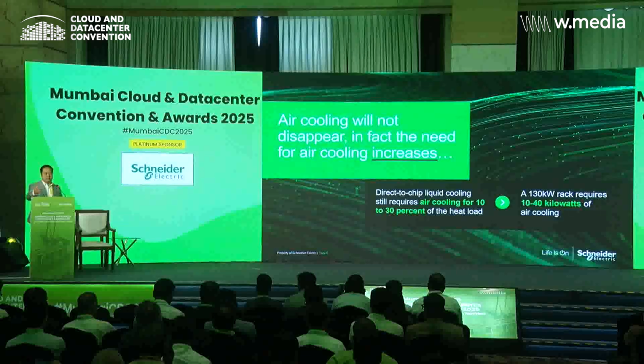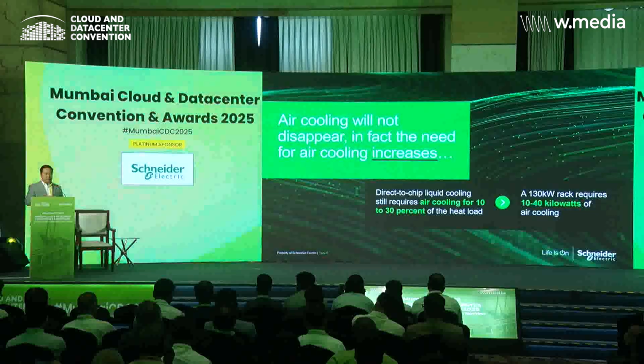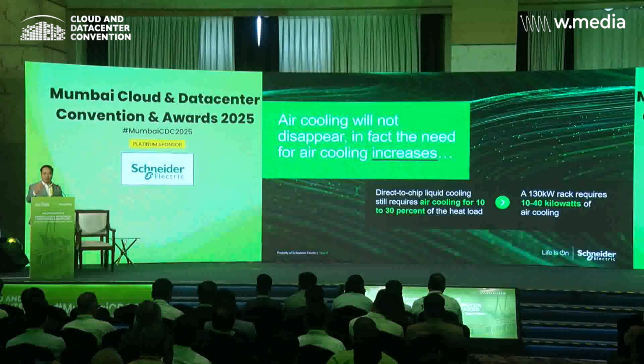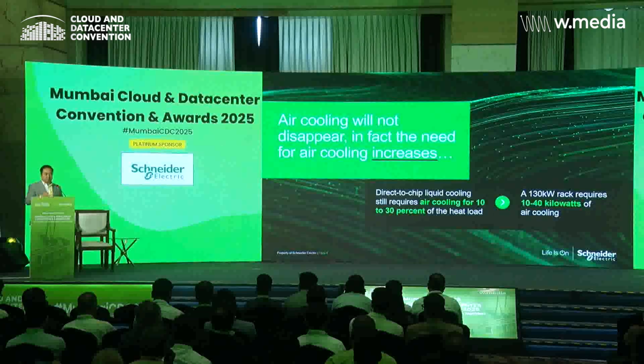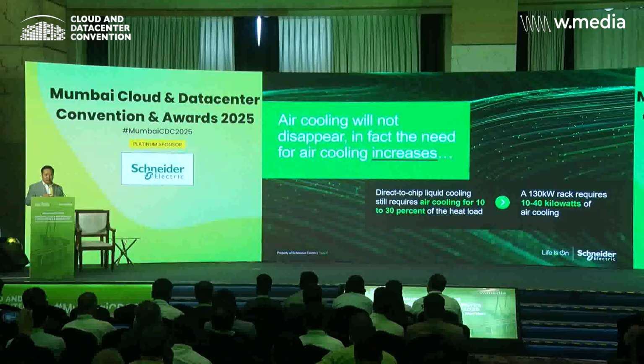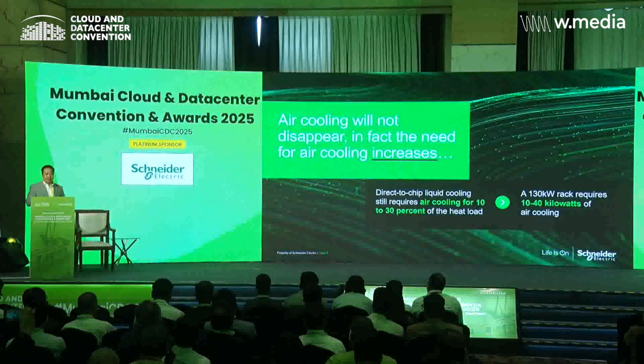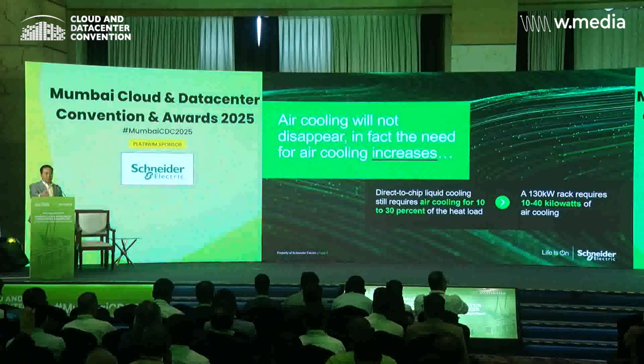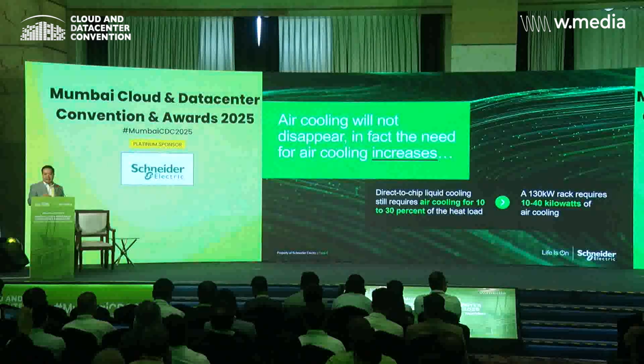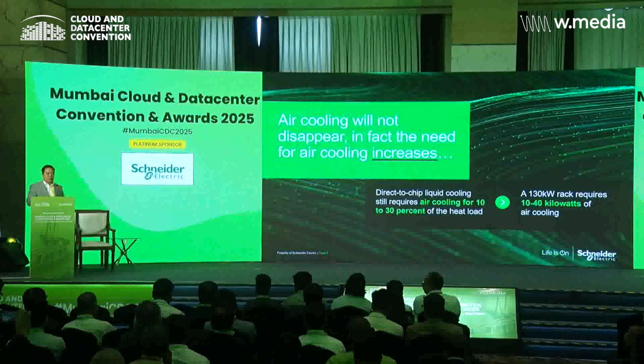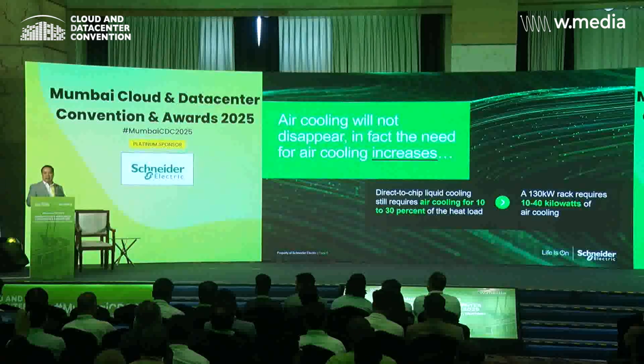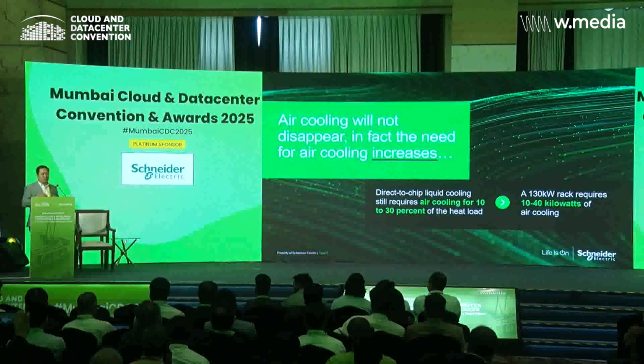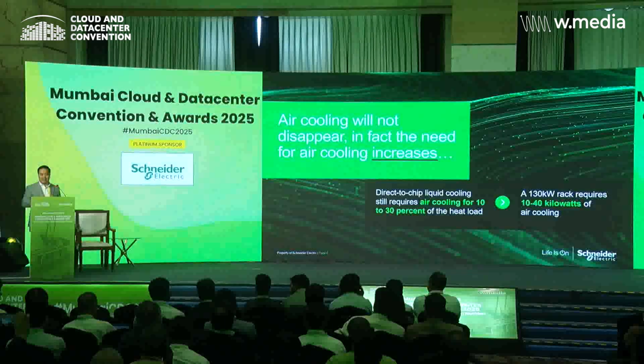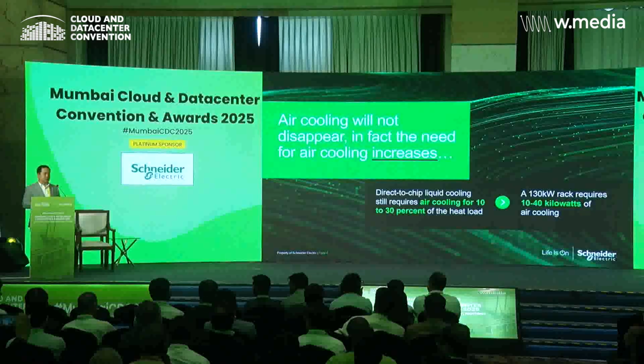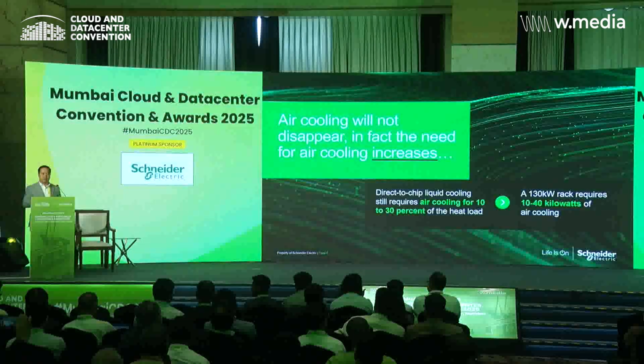As we progress into higher densities, the efficiency of liquid cooling will increase, but the amount of heat per rack will probably stay the same. At a 1 megawatt rack, you'll still likely see 40 kW of residual heat, which means you still have to cool that. And as you know, air cooling at 40 kW or 30 kW a rack is still high performance cooling, so you need the right strategies to cool that.